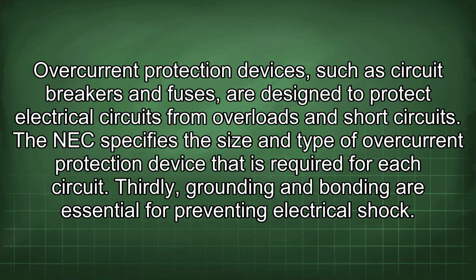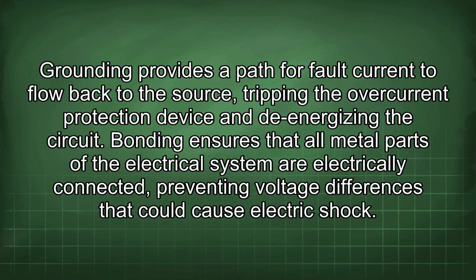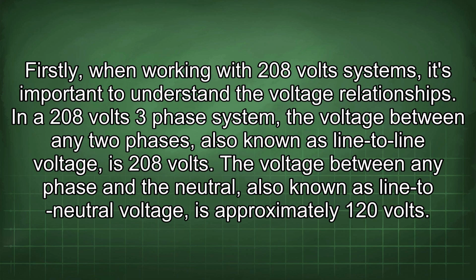Thirdly, grounding and bonding are essential for preventing electrical shock. Grounding provides a path for fault current to flow back to the source, tripping the overcurrent protection device and de-energizing the circuit. Bonding ensures that all metal parts of the electrical system are electrically connected, preventing voltage differences that could cause electric shock. Firstly, when working with 208 volt systems, it's important to understand the voltage relationships.